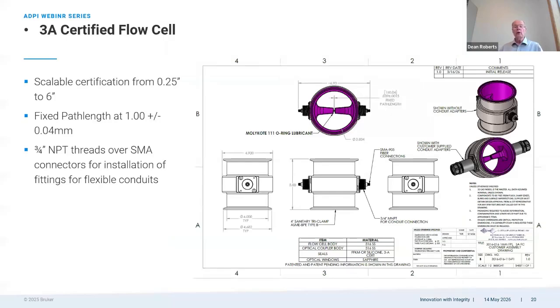Next slide, please. Here are the drawings of the flow cell, and you can see that the topmost on the left is showing you a down the throat view. We have a 1 millimeter path length that is adjustable to 1 millimeter plus or minus 0.04 millimeters. And we actually use a measurement of ethyl acetate as a solvent and compare the peak intensity to verify that the path length is in fact right at 1 millimeter. We've got standards that we've set up for it, and then we compare the absorbance spectrum of each one of the flow cells to the standard, and we can adjust the path length in the factory to minimize those differences. That is one of the things that helps transfer calibrations from one instrument to the other.